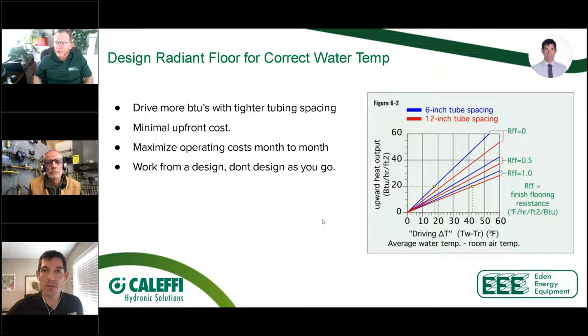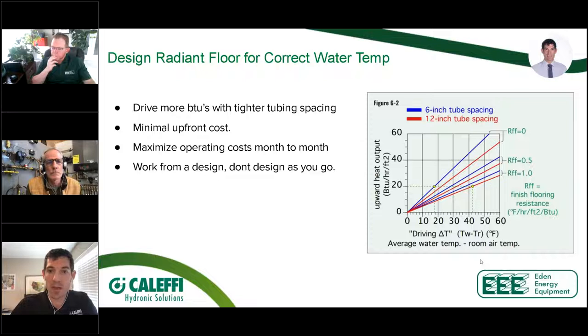Any thoughts on that, Max? What was the spacing that we did in your shop? Did we do 6 or 9 inch? Yeah, 6 inch. I mean, it doesn't need that. If you looked at a warehouse garage example, if you put it into LoopCAD with one of the manufacturers, it might say, no, 12 or 18 is fine. But to go with the lowest temperature, it's going to be faster responding. It's going to be really comfortable if you're in there, not that you're in there with bare feet in the shop, but it's a good fit.